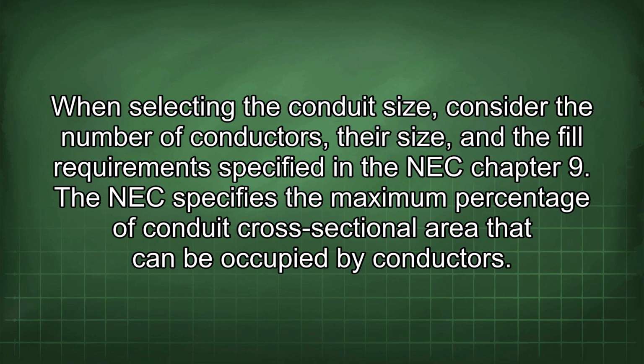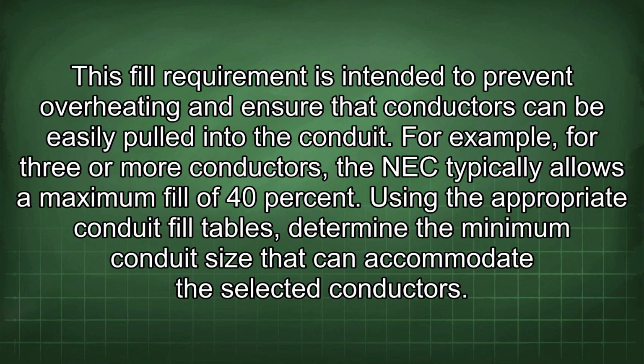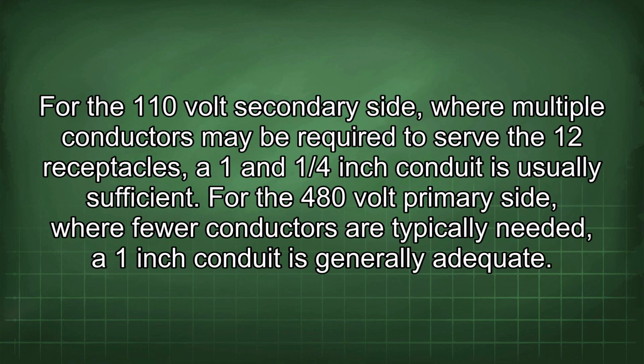The NEC specifies the maximum percentage of conduit cross-sectional area that can be occupied by conductors. This fill requirement is intended to prevent overheating and ensure that conductors can be easily pulled into the conduit. For example, for 3 or more conductors, the NEC typically allows a maximum fill of 40%. Using the appropriate conduit fill tables, determine the minimum conduit size that can accommodate the selected conductors. For the 110-volt secondary side, where multiple conductors may be required to serve the 12 receptacles, a 1 and 1/4-inch conduit is usually sufficient. For the 480-volt primary side, where fewer conductors are typically needed, a 1-inch conduit is generally adequate.